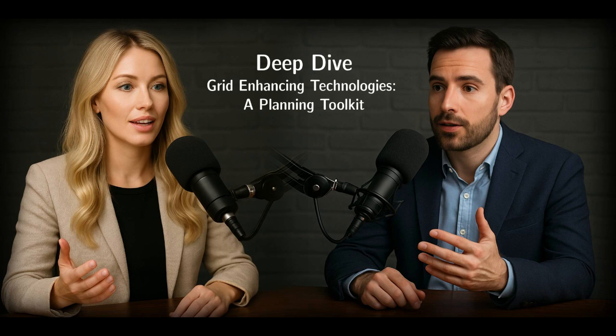What about pumped hydro storage? That's an older technology, but still relevant here. Very relevant. Pumped hydro storage involves large-scale installations, usually 100 to maybe 3,000 megawatt, much longer duration too, 6 to 20 hours of storage typically. What transmission services can pumped hydro provide? It offers significant inertia, which is crucial for grid stability, especially with more inverter-based resources like solar and wind. It provides stability services, voltage support, and even black start capability, the ability to restart parts of the grid after an outage.